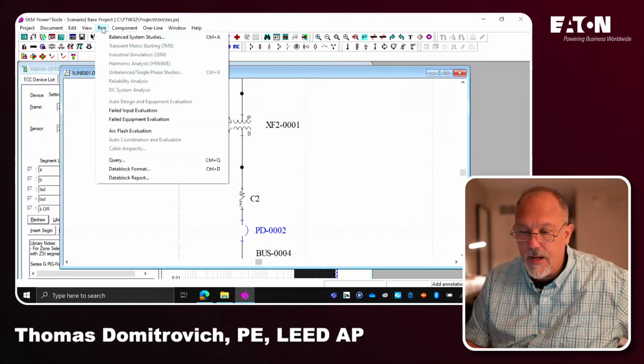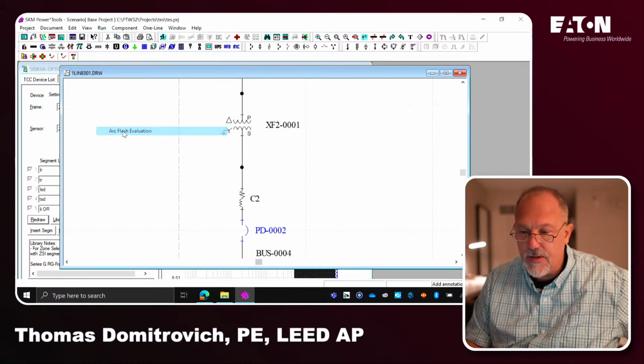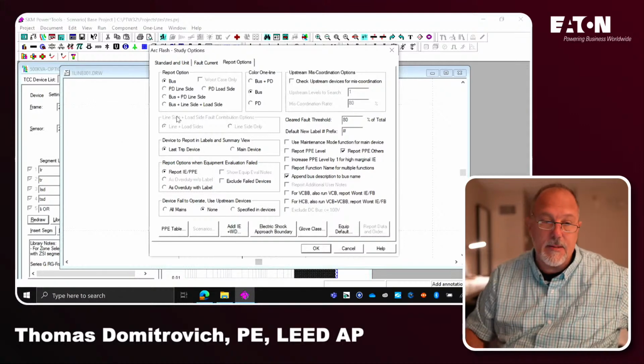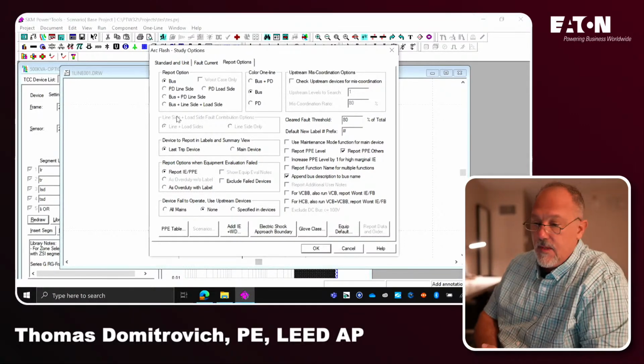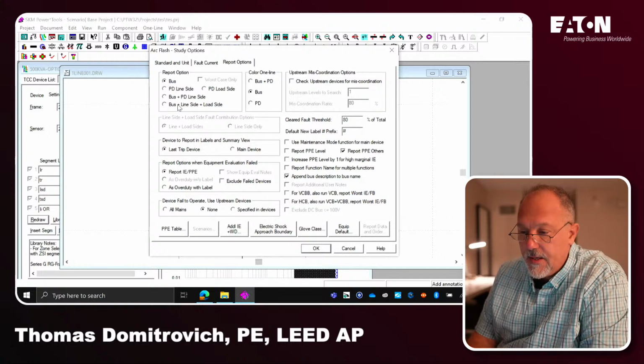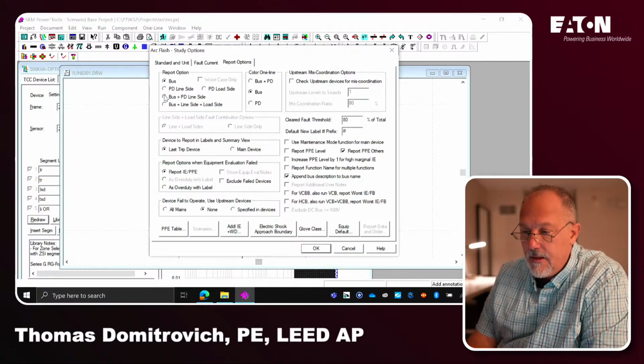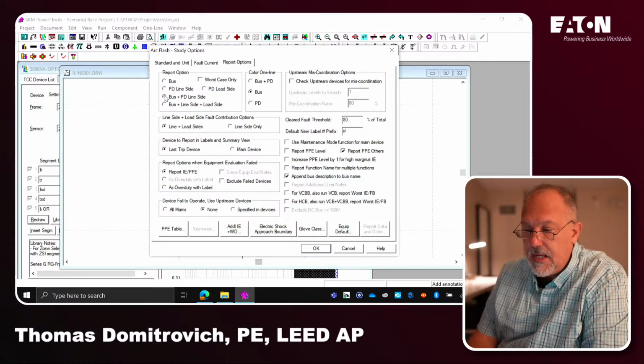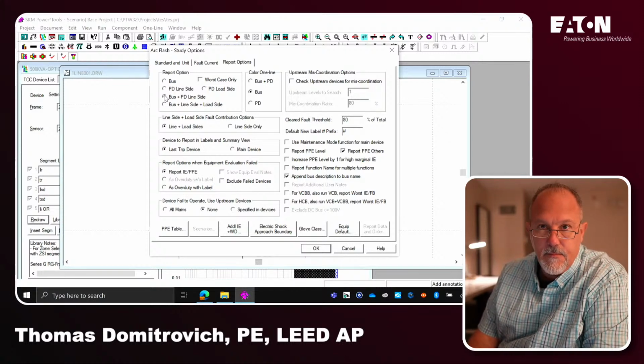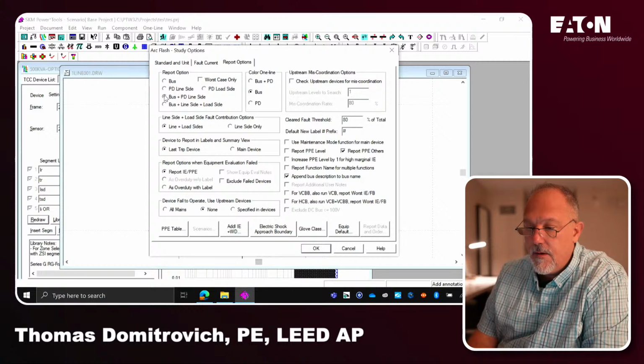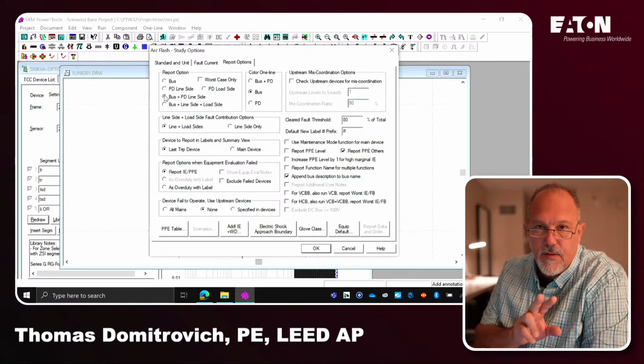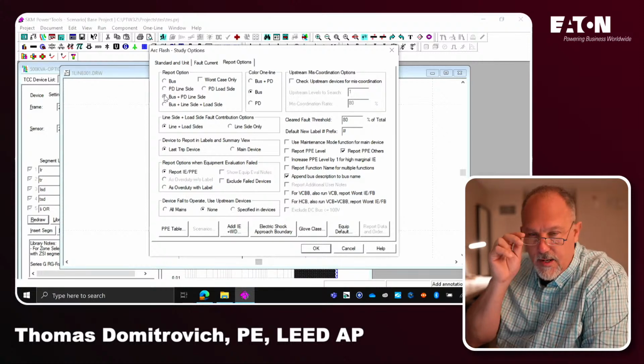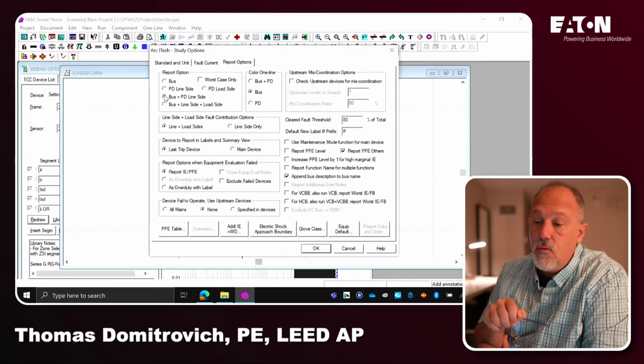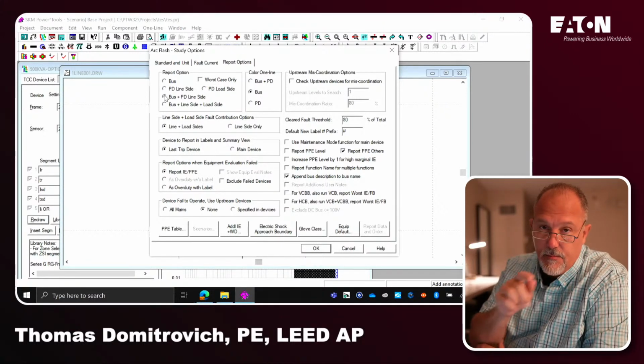Now I'm going to run my arc flash evaluation. Now, okay, so I've got to pick some stuff here. I am going to pick, here's what I'm going to, bus plus PD line side. What that'll give me is two numbers for arc flash on the secondary. One based upon the main overcurrent device. Ooh, and the second based upon the upstream.